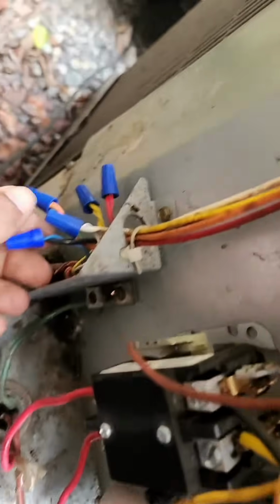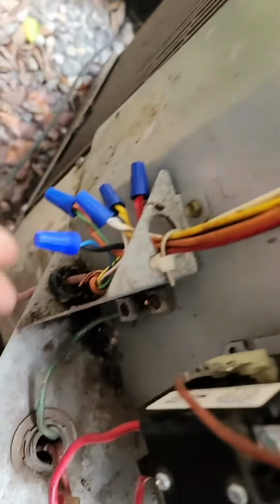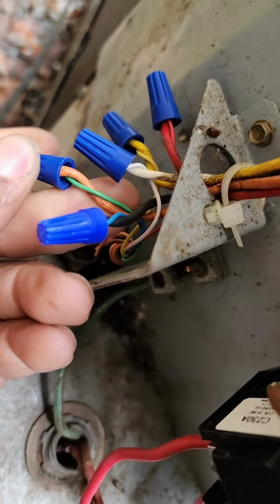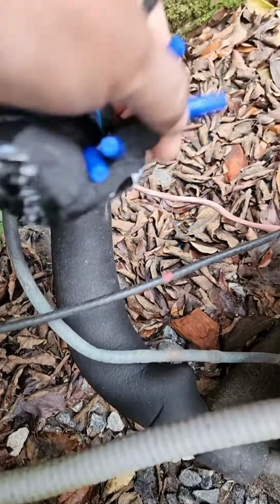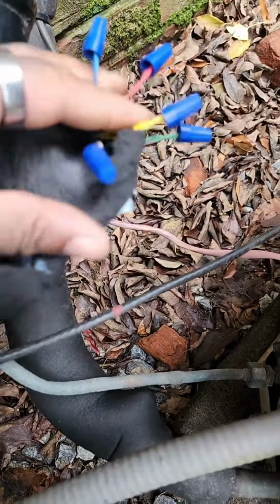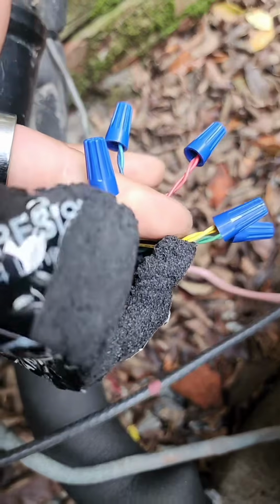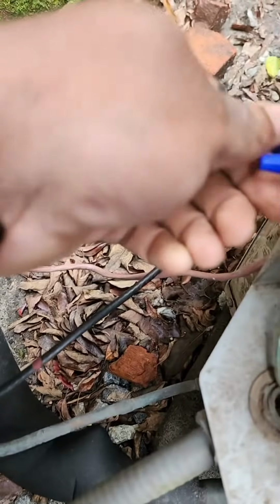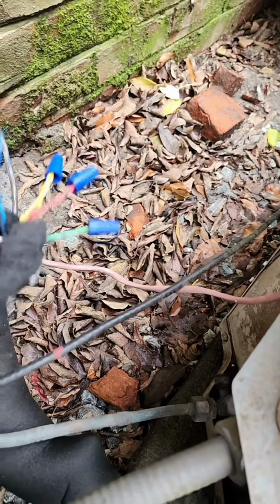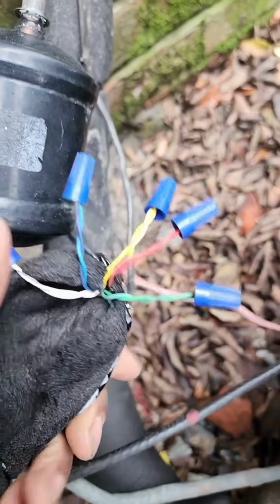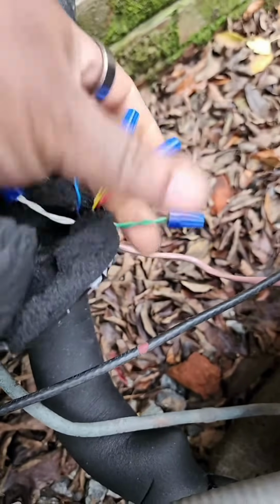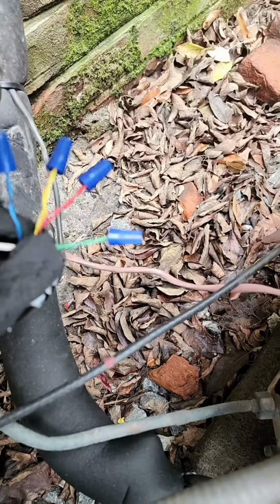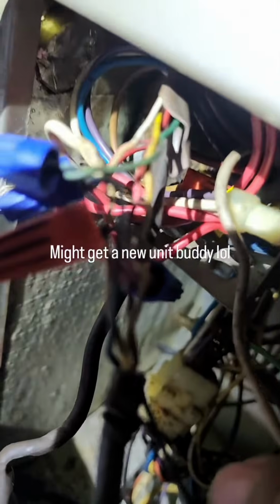Alright, so we're back. I grabbed 2 transformers from the storage unit. Alright, so yeah, they're using green as orange. There's a little splice here, and they wired up everything color to color. So that blue wire that I hooked up, that I'm using as orange, should be connected to green up there at the air handler. So let's go look at that. And then as I go through the process of elimination, I ain't trying to blow up another transformer. And so green is orange and blue is orange. Green, orange for outside, blue, orange inside. Yeah, so blue and green's connected, going to the outdoor unit.